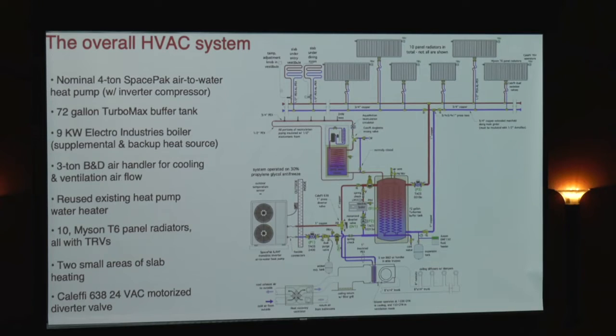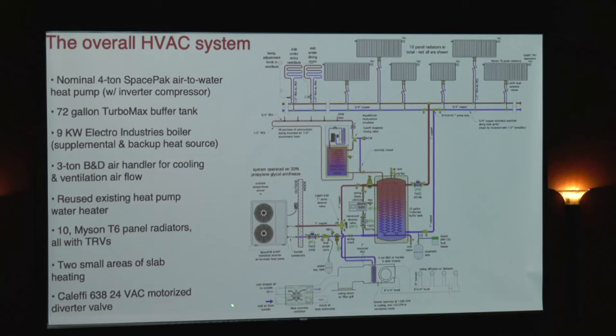A little hard to see it here, but here's the heat recovery ventilator down here. I think, if I remember right, this was either April Air or Renew Air, or one of those. Obviously, there are many of them on the market right now. And the outdoor air comes in, goes through the core of the HRV, and is injected into the return header of the air handler.